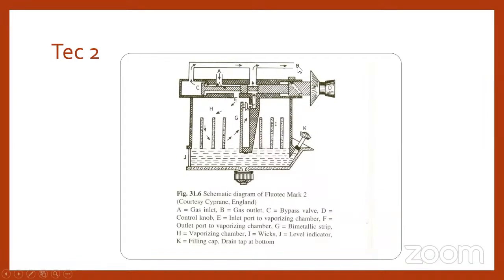To minimize the pressure effect and pumping effect, there is a pressure control valve located in this place. It is a unidirectional valve, so it allows air only in this direction. It prevents the reverse flow of any gas that is present in the pipeline. So whenever we bag the patient, the excess amount of fresh gas or mixture will not come back to the vaporizing chamber because of this pressure valve. So this is the safety mechanism that is incorporated in the Tec 2 system to prevent the pumping and pressurizing effect.